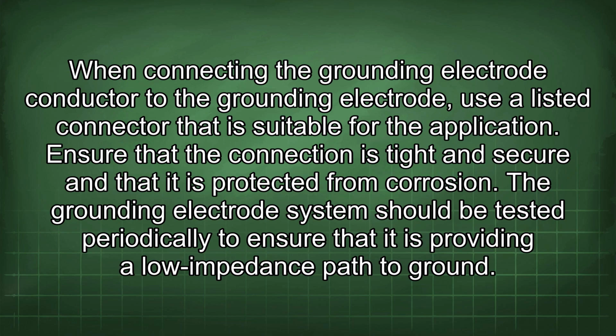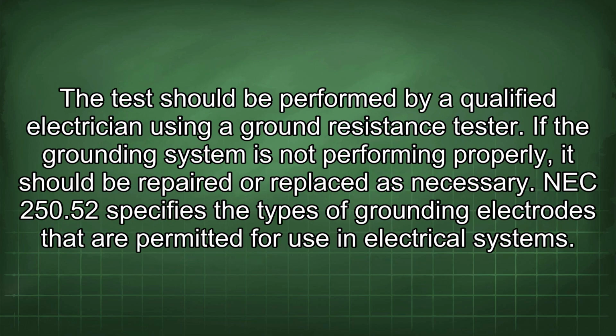Ensure that the connection is tight and secure and that it is protected from corrosion. The grounding electrode system should be tested periodically to ensure that it is providing a low impedance path to ground. The test should be performed by a qualified electrician using a ground resistance tester. If the grounding system is not performing properly, it should be repaired or replaced as necessary.